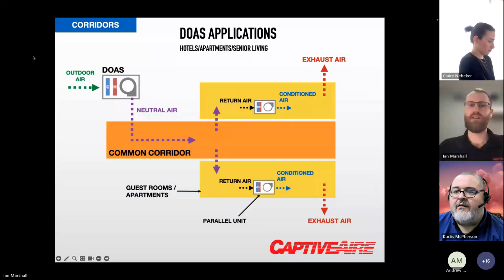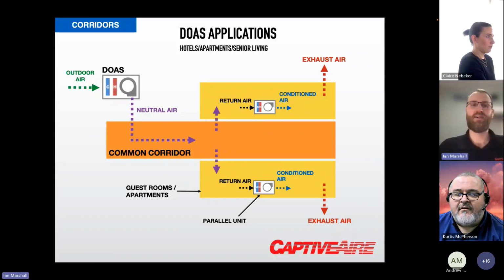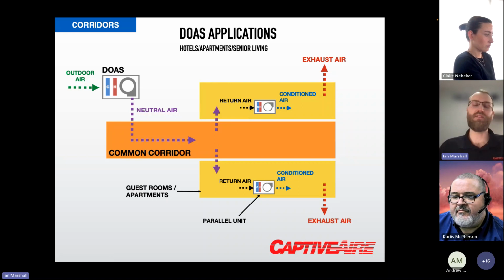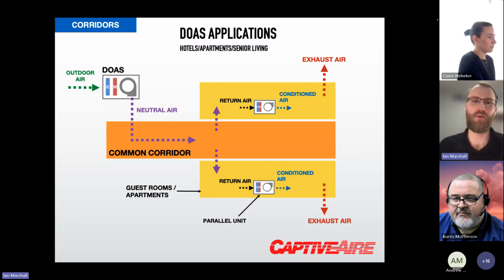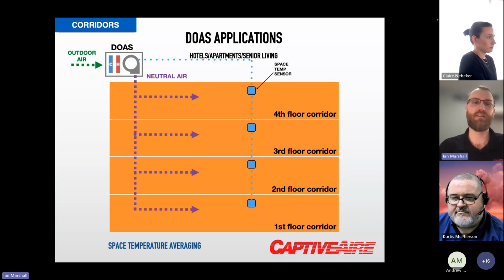So this is just a simple diagram of the hotel corridor application that we see very commonly. We are pressurizing that corridor with 100% outside air, and each individual guest room would have negative pressure in it from a bathroom exhaust. So essentially that corridor is positively pressurized and each room is negatively pressurized. So you're bringing in the ventilation through the door or through a grill in the space. And those individual spaces have their own heating cooling units like PTACs or what it might be. And essentially we're providing neutral supply air to the space continuously. So it's a very simple, straightforward, and really common application we'll see with DOAS.